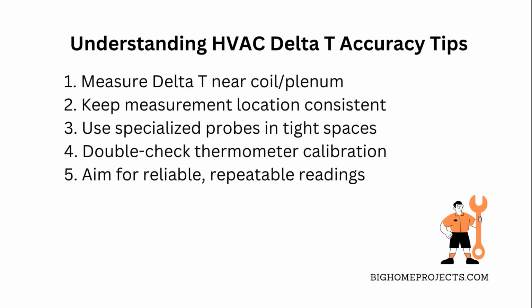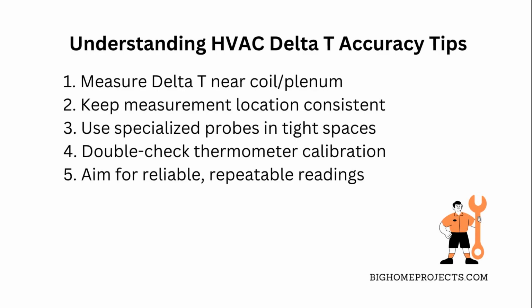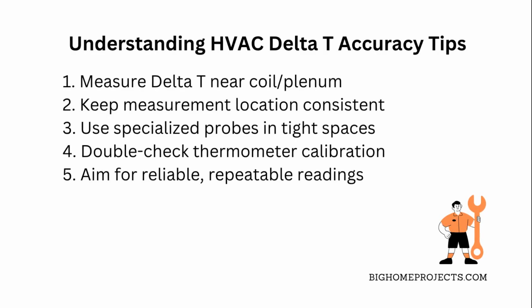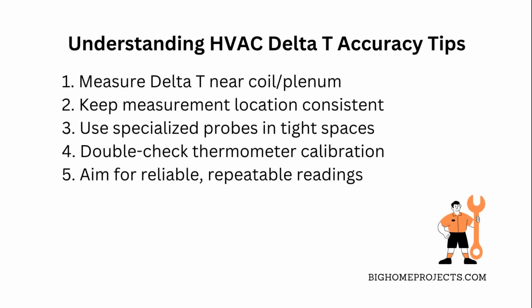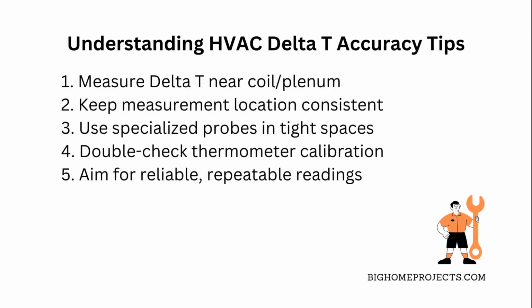big time. Like, measuring too far from the coil or plenum means you're not getting real numbers because the air temperature changes as it moves through the ductwork. Always try to take your temperature readings as close to the coil or plenum as you can. That's where the air's freshest and closest to the real deal.